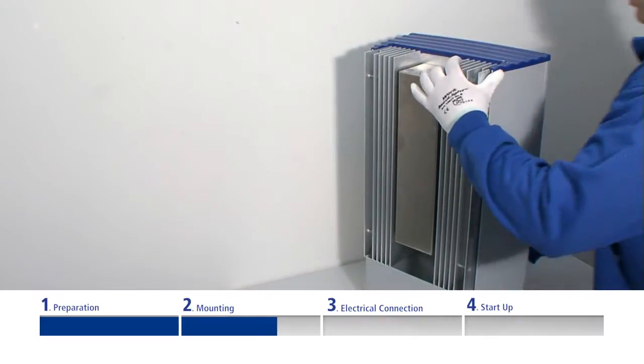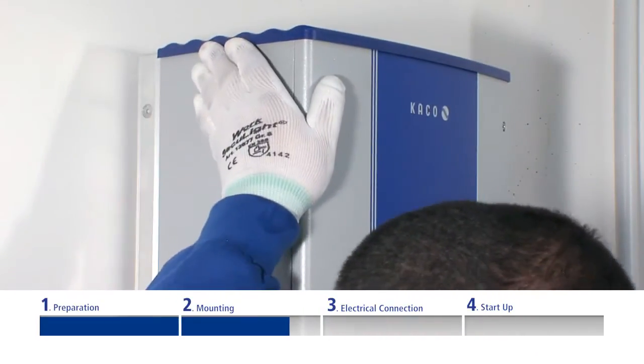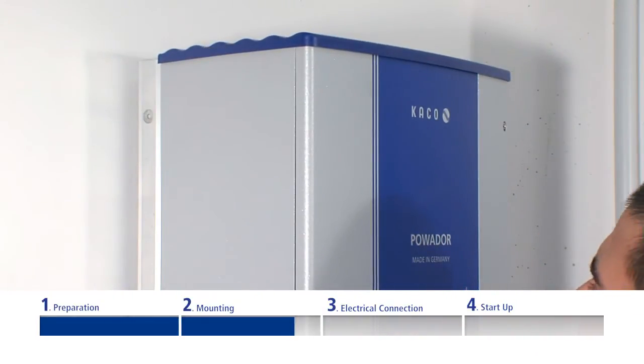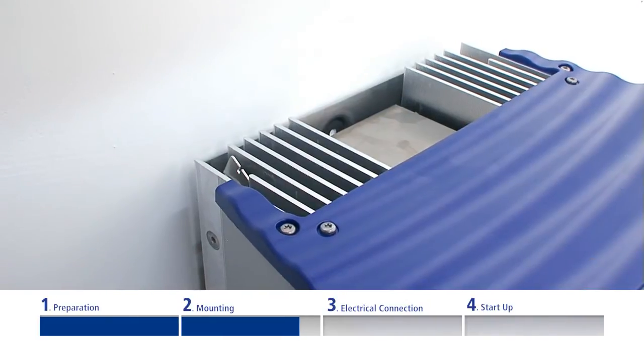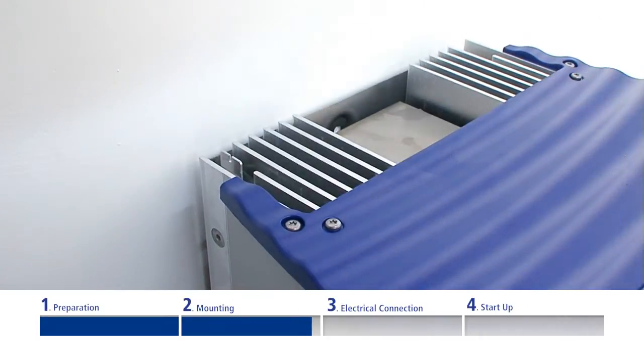Mount the inverter on the mounting bracket so that the pegs in the heat sink rest in the notches. Finally, lock the safety catch. To do this, slide the upper end of the catch towards the wall until the groove runs parallel to the wall.